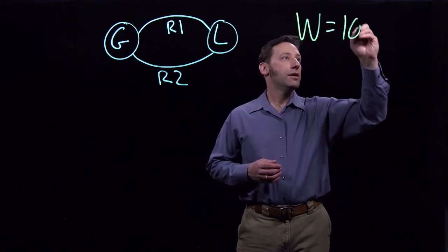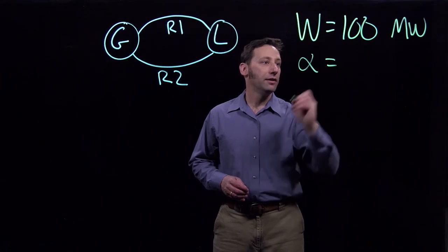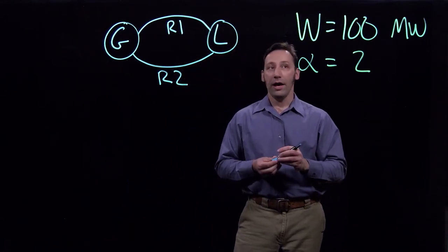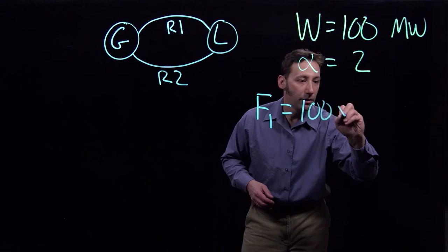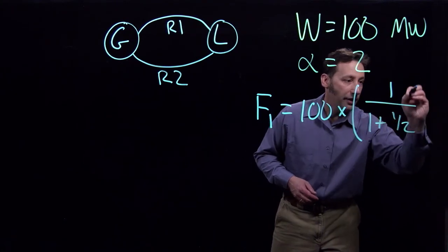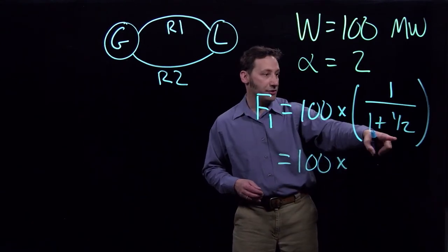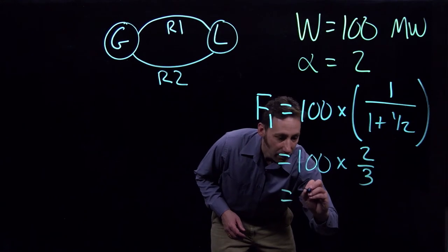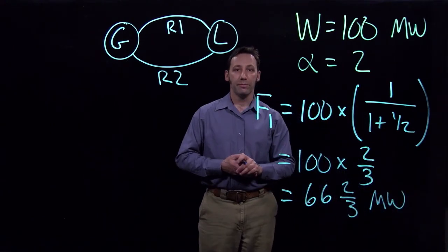As an example, let's take w equal to 100 megawatts and alpha equal to two. The flow on line one is going to be equal to w times one over one plus one half. So this is going to be equal to 100 times the distribution factor, which in this case is two-thirds. That gives us 66 and two-thirds megawatts flowing on line one.